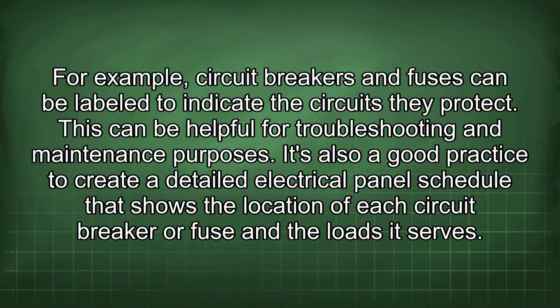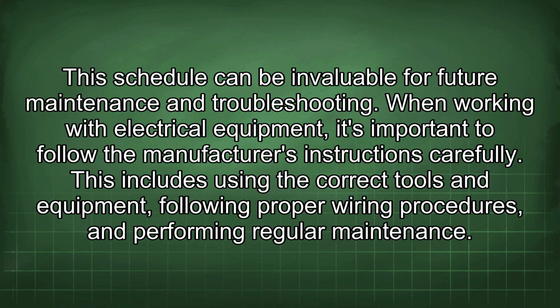It's also a good practice to create a detailed electrical panel schedule that shows the location of each circuit breaker or fuse and the loads it serves. This schedule can be invaluable for future maintenance and troubleshooting.